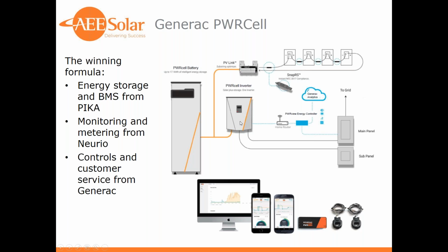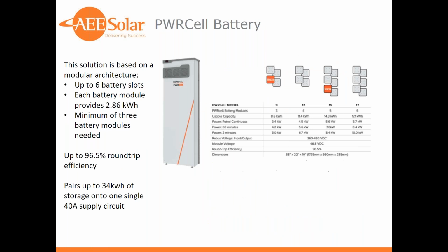Back to the inverter, I mentioned it is capable of simultaneously powering AC loads while charging batteries. The battery cabinet and solution is pretty smart, so let's get into that. The battery solution is based on a modular architecture. One cabinet is capable of storing and powering up to 6 battery modules. Each module provides 2.86 kilowatt hours. There is a minimum of 3 modules needed to have a viable system. But from there, I won't say infinite, but you've got a ton of flexibility on how much is the right amount of storage per application. Because you're dealing with smaller chunks, you can really fine tune the amount of storage.